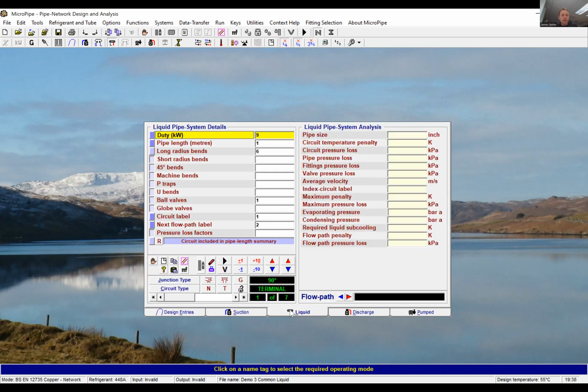And this is the awesome thing about White Rose when calculating liquid lines. Hit that play button again. There you go. It's as simple as that. So we'll go to 2 and 3 will be the same. They'll be ½ inch. Real happy with those velocities, 0.6.